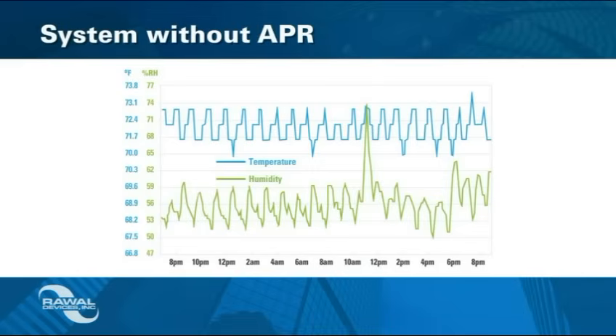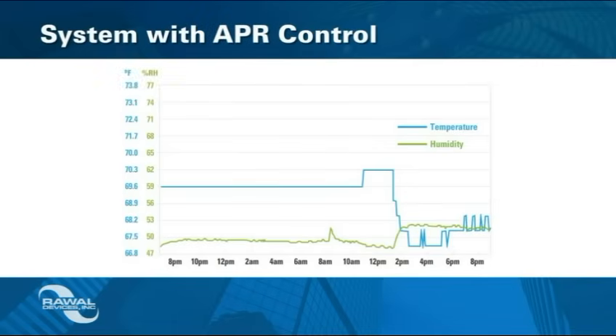In this example at a hotel in Florida, the graph shows the results of failing AC equipment. Wide swings in temperature and humidity caused mold to grow on the room's beds and other surfaces. When the APR Control was installed, the AC equipment precisely controlled the room's temperature and humidity.